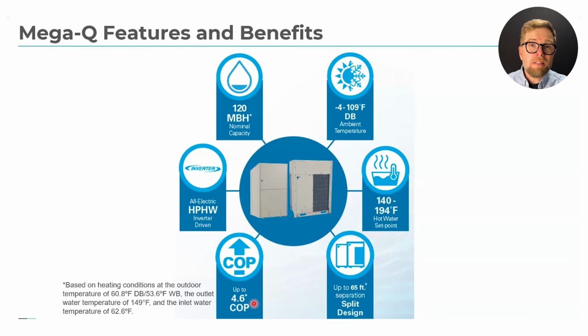This system operates in ambient conditions from -4 degrees Fahrenheit to 109 Fahrenheit, delivering hot water temps of up to 194 degrees Fahrenheit. Oh, and if you are in a region with energy efficiency programs and rebates, this system boasts COPs up to 4.6, giving you significantly better efficiency than your typical electric or gas boiler. Think about that difference in the long term in an operation scenario.